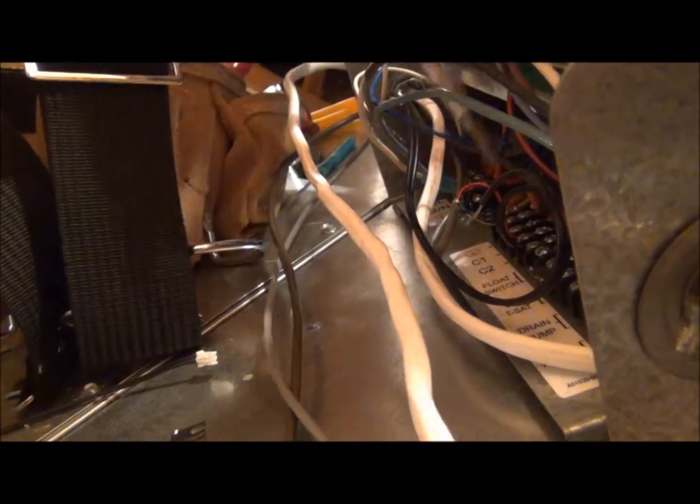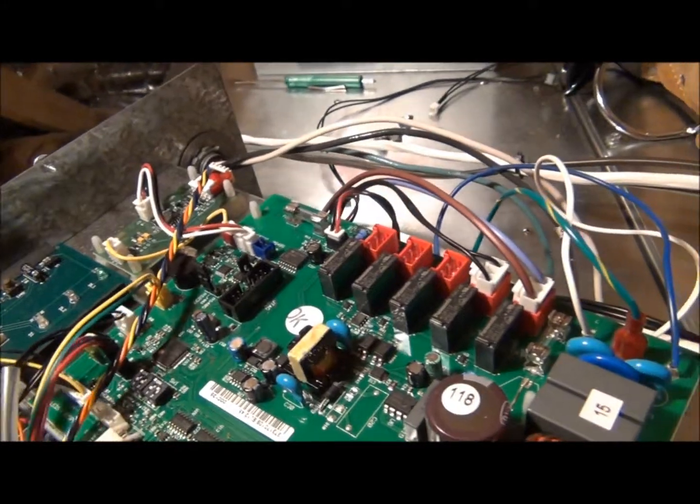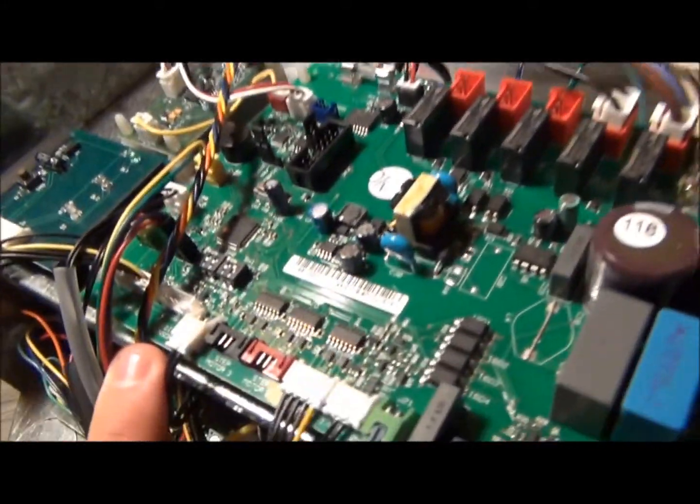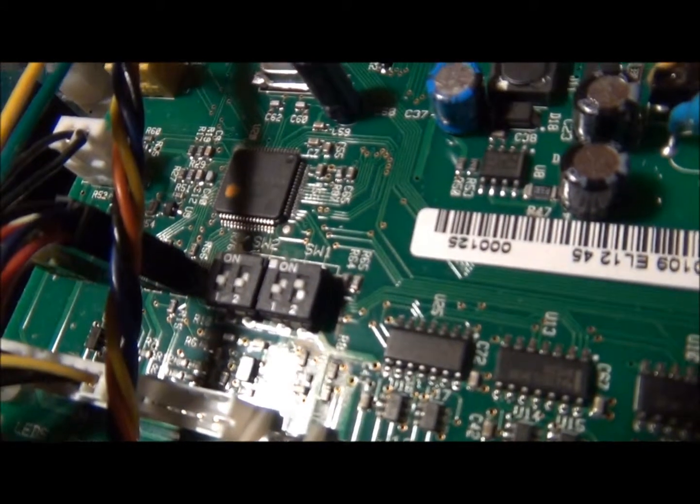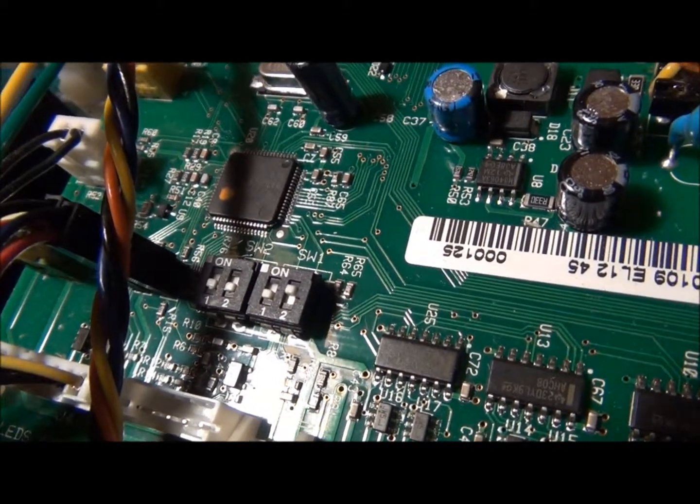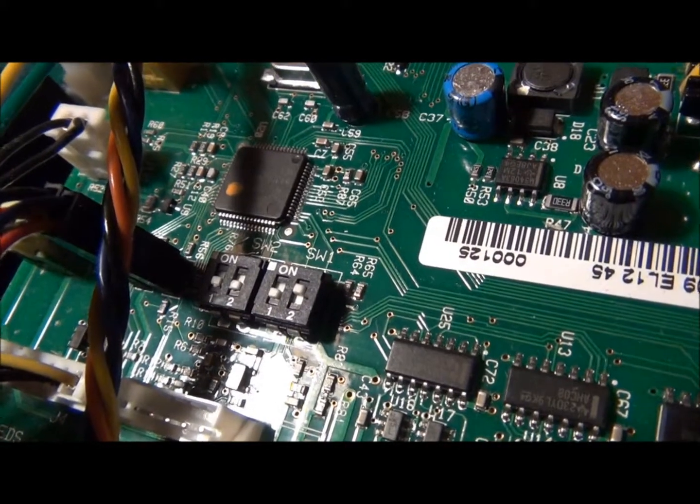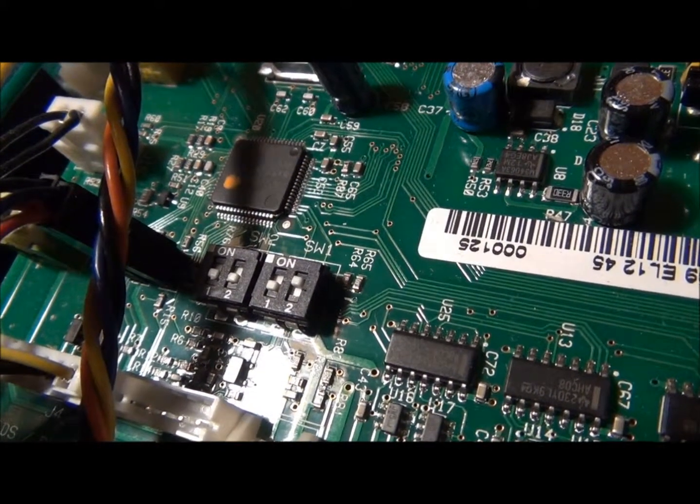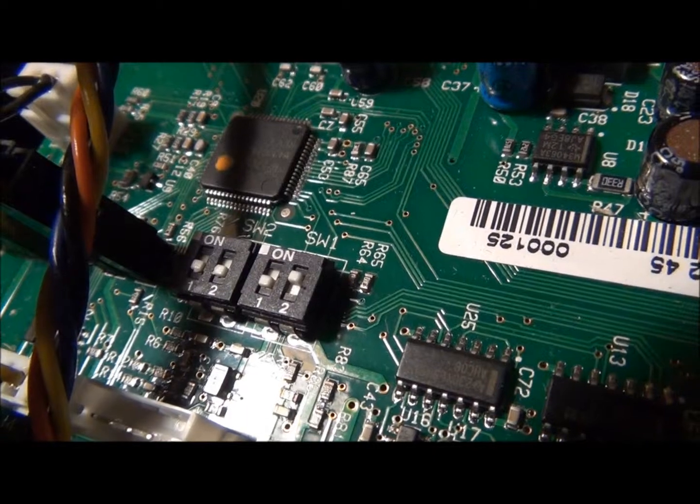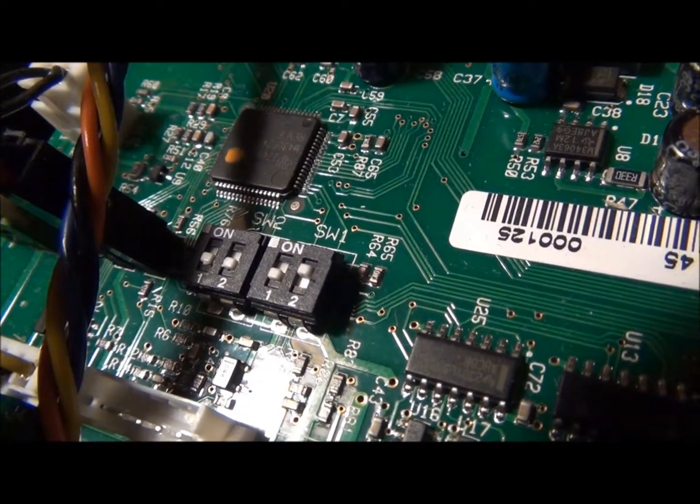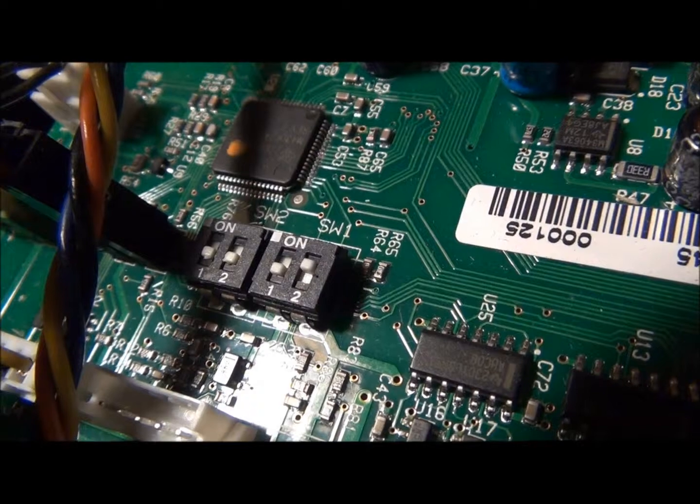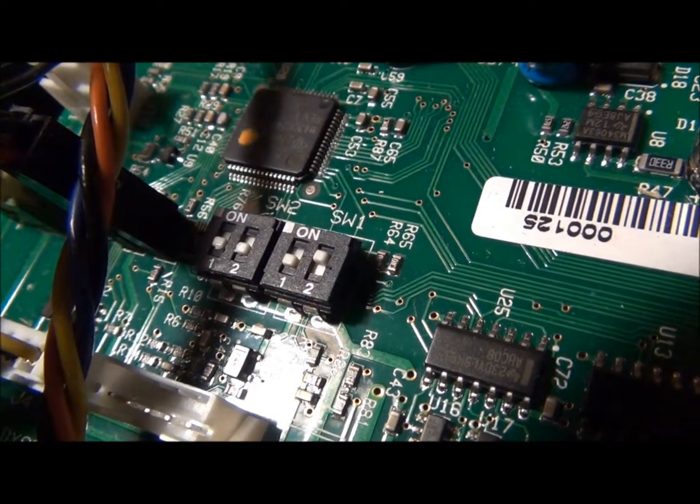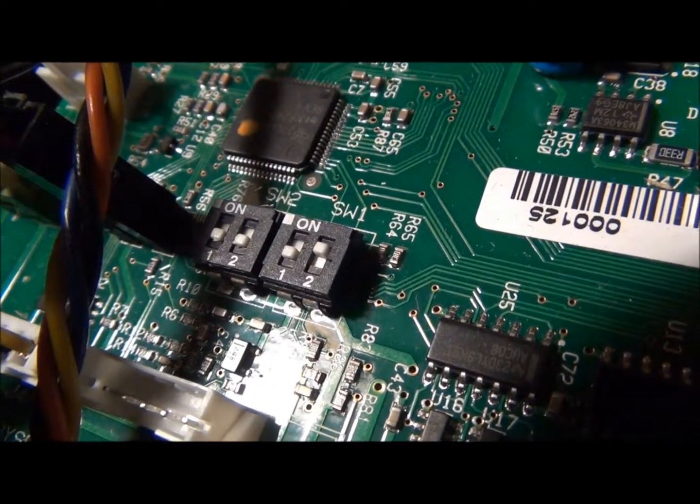On the indoor B board for the i-series unit there are two switches labeled switch 2 and switch 1 from left to right. Switch 2 tells us what refrigerant circuit we're hooked up to, whether circuit 1, 2, 3, or 4. We're hooked up to circuit number 1, so we set that to the factory default which is off, off.